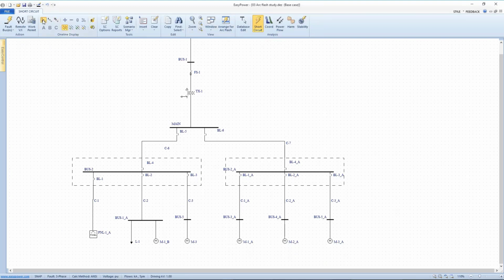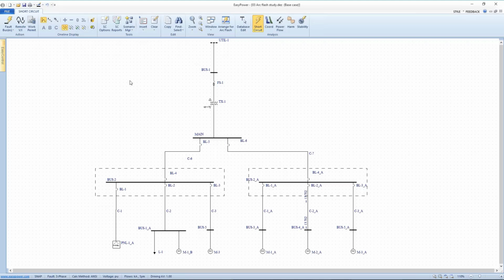First thing I want to do is to look at the half cycle, 3-phase fault. Now, we haven't talked about it, but there are other types of faults that could be applied to the system, and they are important as part of a short circuit study to understand how the system will respond to a ground fault or a line-to-line fault. But for the purposes of arc flash incident energy, they're not taken into account because it's a model. The IEEE model only applies to balanced 3-phase faults at this time.